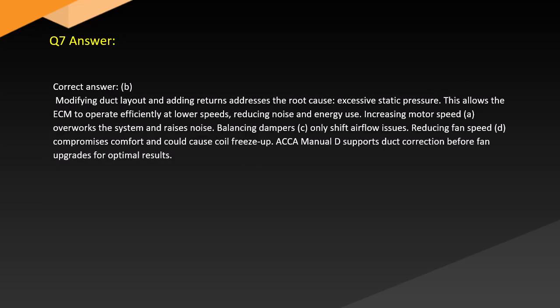Answer. Correct answer: B. Modifying duct layout and adding returns addresses the root cause, excessive static pressure. This allows the ECM to operate efficiently at lower speeds, reducing noise and energy use. Increasing motor speed (A) overworks the system and raises noise. Balancing dampers (C) only shift airflow issues. Reducing fan speed (D) compromises comfort and could cause coil freeze-up. The ACCA manual supports duct correction before fan upgrades for optimal results.